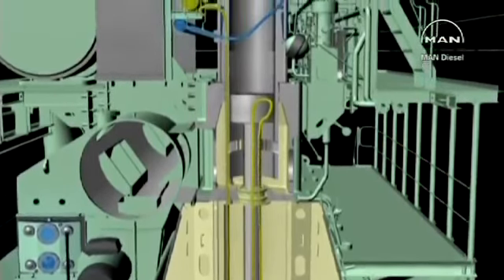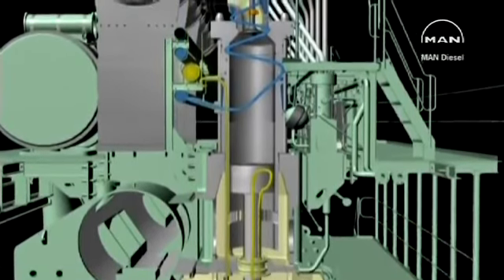This is possible because there's a drop in temperature as the heat passes from cylinder gas to metal. Even though the gas is in violent motion inside the cylinder, the boundary layer close to the wall forms a rather effective insulating layer where the temperature falls rapidly. Through the wall itself, the temperature falls evenly, but the heat transfer to the cooling water is controlled by the local boiling point of the water in contact with the wall, the so-called micro-boiling phenomenon. The high wall temperature causes a local boiling, which is able to absorb relatively large amounts of heat. Small steam bubbles are formed, which immediately break loose from the surface and condense in the surrounding water. Due to this, the wall temperature is almost independent of the transmitted amount of heat, provided that the water temperature is safely below its boiling point.